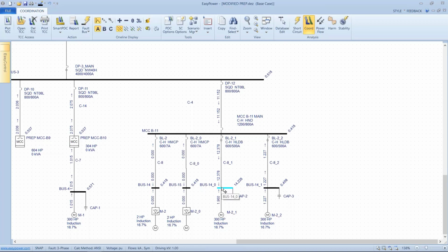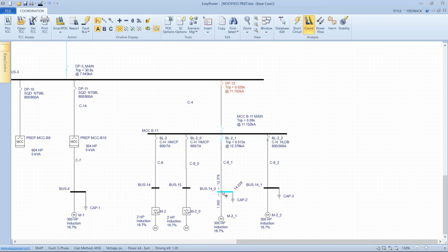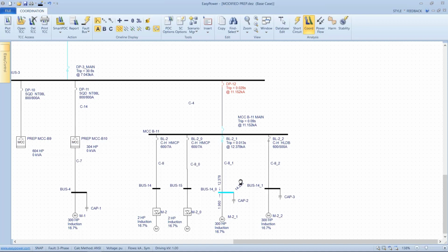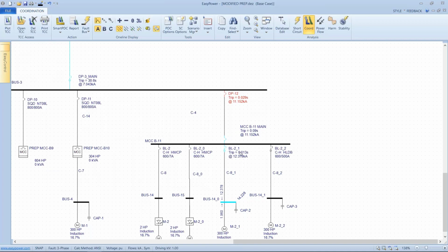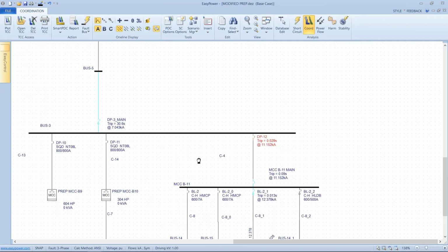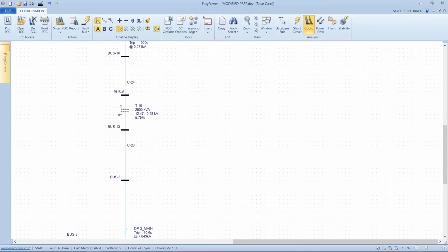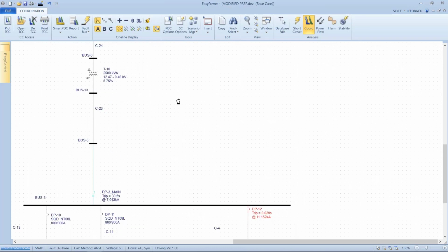Again, this would play into equipment duty, and that's why I want to make sure that each of these buses has a rating set from the manufacturer. Now, once I'm in this configuration, I can look at my sequence of events, and the tool will indicate what the upstream tripping device is from each of these if a fault on this bus. Now this will work on these other elements, but because we're limited by which bus can be faulted, we get potentially similar results. So if this bus faults, this breaker will trip in 13 milliseconds. This breaker will trip in 90 milliseconds. This breaker will trip in 29 milliseconds, which is why we're showing a red control value. This breaker will trip in 30 seconds, and then we can go up to the fuse, which will not trip for that single bus fault.